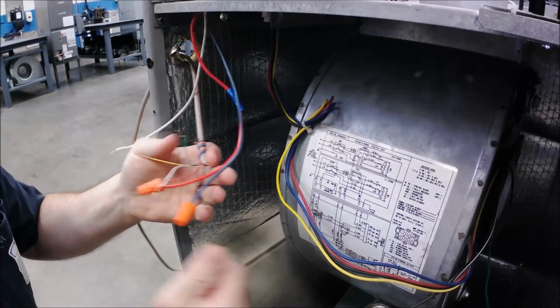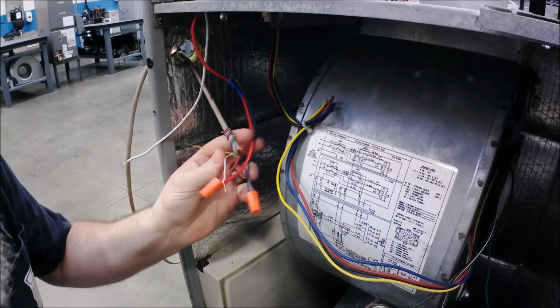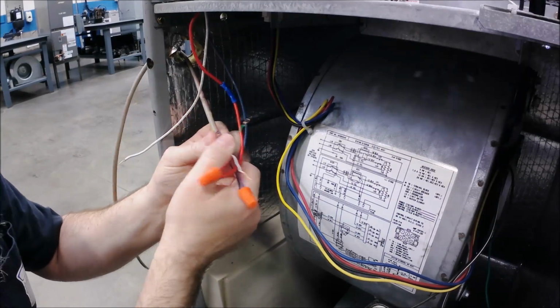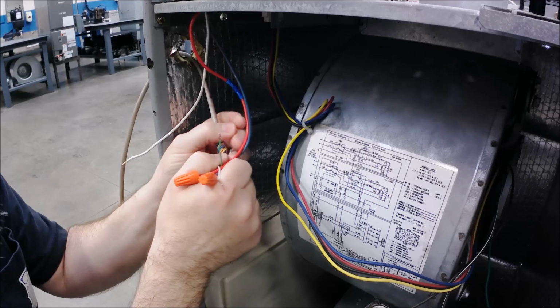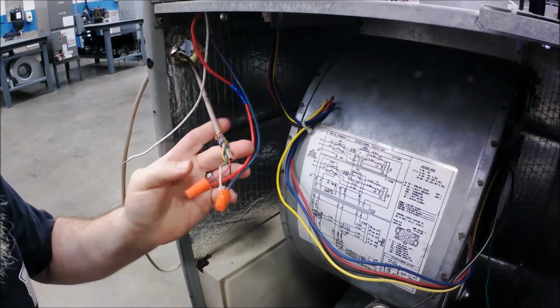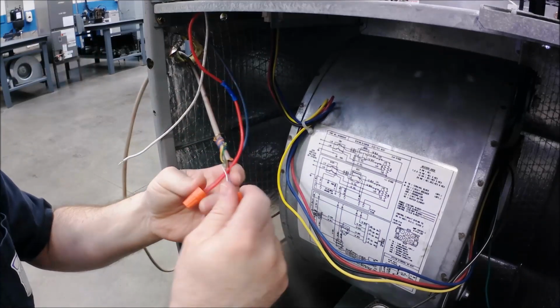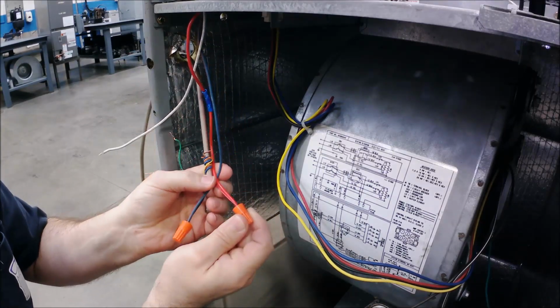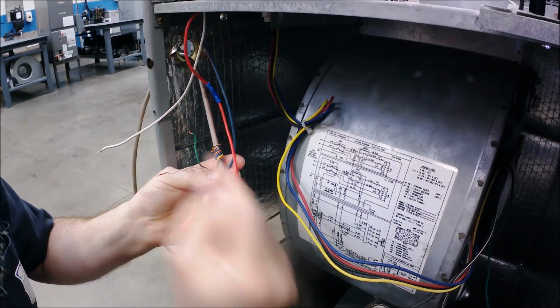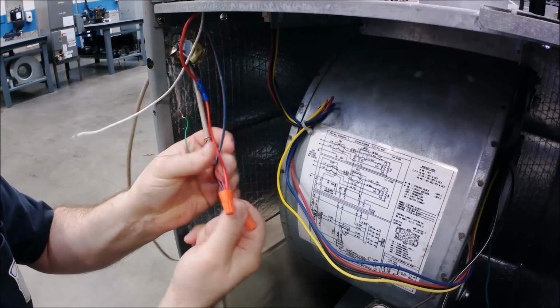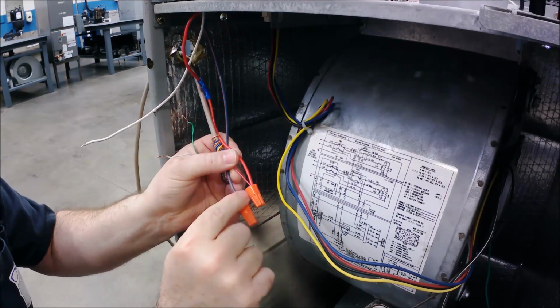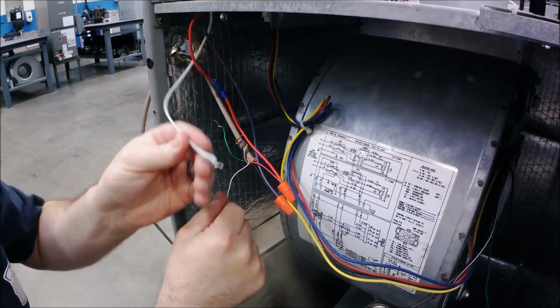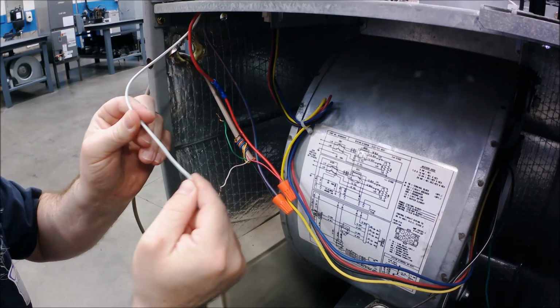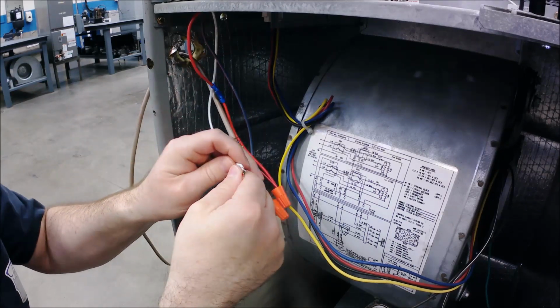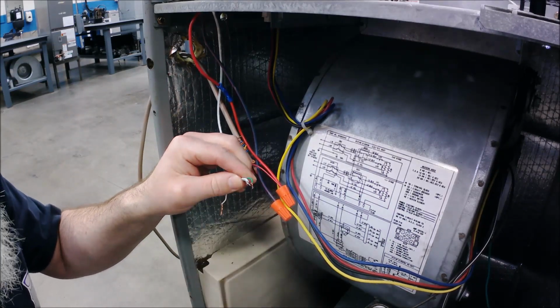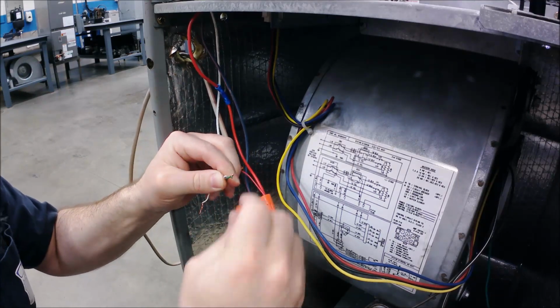Now this is a standard setup here. We're not using the Y circuit because I've just taken this air handler, and it's only going to be used with electric heat, so we're going to wrap the Y circuit around from the thermostat itself. Okay, so I've got my red from your thermostat wire going to the fuse holder, so that's the hot connection. I've got my black wire here at the thermostat that is tied to the common connection. What we're going to do now is, remember there's a white with a blue stripe. That connection goes to the rib relay, and it is now our indoor fan circuit or indoor fan relay circuit.